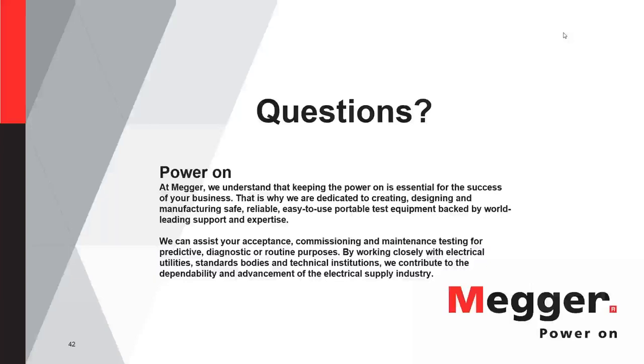Okay, I can answer that. And Henning might want to chip in on top of it because he's a doctor of science and a chemist, so he knows all the details on that. What I meant with this is in terms of pure dielectric properties, XLPE has the better dielectric properties than EPR. This is also the reason why all the high voltage transmission cables are typically made with XLPE. It has less losses and a better permittivity. Now, EPR is a compound. It has one advantage that is very popular in the field, which is its mechanical properties, because it's much more flexible than XLPE. But overall, XLPE is the standard installation all over the world.